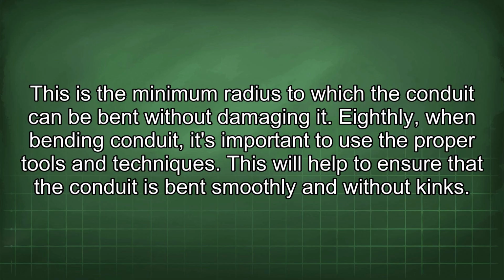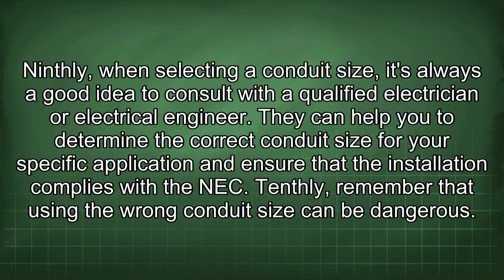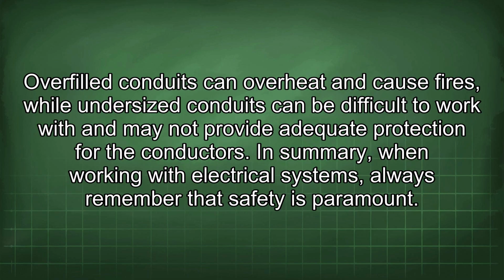Eighthly, when bending conduit, it's important to use the proper tools and techniques. This will help to ensure that the conduit is bent smoothly and without kinks. Ninthly, when selecting a conduit size, it's always a good idea to consult with a qualified electrician or electrical engineer. They can help you to determine the correct conduit size for your specific application and ensure that the installation complies with the NEC. Tenthly, remember that using the wrong conduit size can be dangerous. Overfilled conduits can overheat and cause fires, while undersized conduits can be difficult to work with and may not provide adequate protection for the conductors.